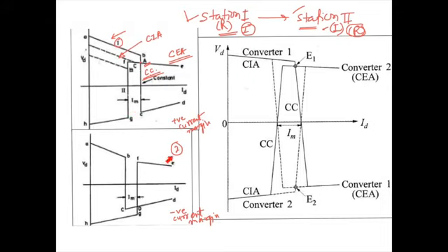Now figure 2 represents that the inverter station, that means station 2, is now acting as a rectifier and station 1 is acting as an inverter. That means there is now power reversal. Under this condition, the operating point is D, where the current reference for inverter is now more than current reference of rectifier.